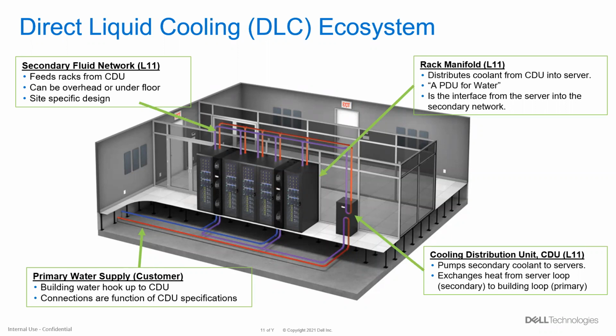So in this case, the customer water could be a range of temperatures. There's a requirement for a maximum temperature and a minimum flow rate, which is well in the realm of what facilities managers are used to providing. But the two loops do not interact, and that's important because the coolant loop needs to remain very clean, pure, closed loop and go through extensive filtration so that when it goes through the cold plates, there's no debris that can get caught up and cause any blockages. As long as it's isolated from the facility loop, that cleanliness will be maintained.